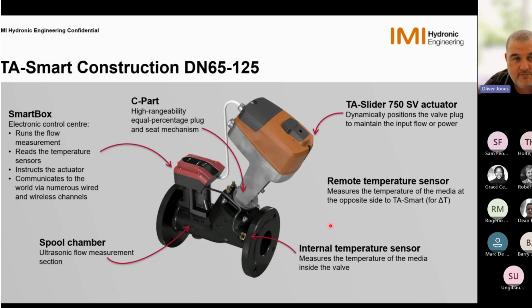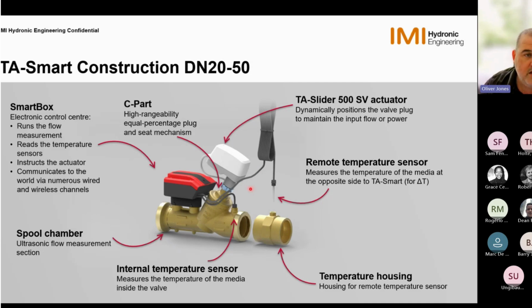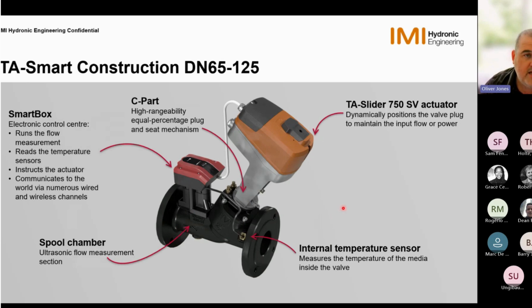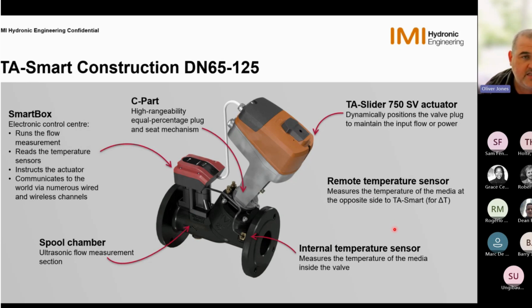We also have a secondary remote temperature sensor, which isn't shown on this image, unfortunately. But again, like the previous one, we have a secondary line that comes out next to it with the same amount of cable, and this is to be mounted on the opposite side. The only difference with the flanged version is we don't actually supply a housing. So that has to be built into something else. So maybe a test point, and you screw the temperature sensor into that, or a PT 1000 pocket.